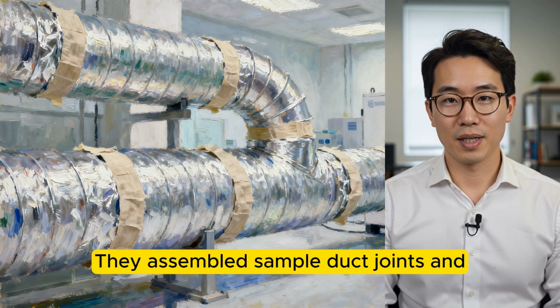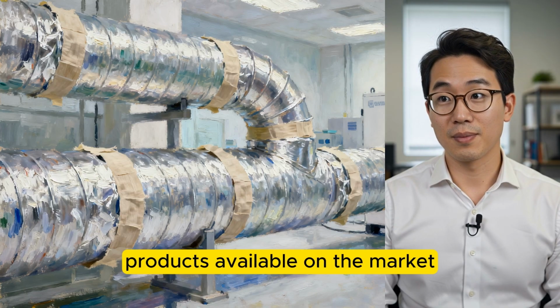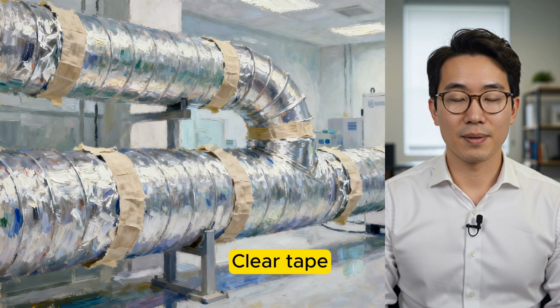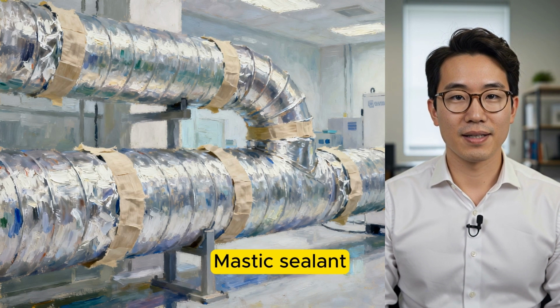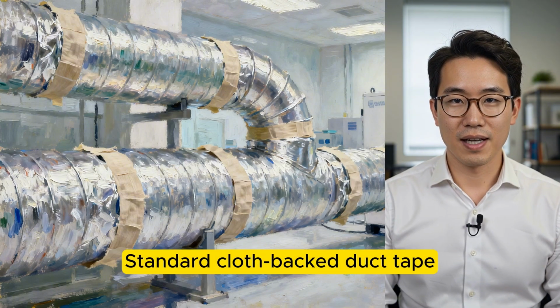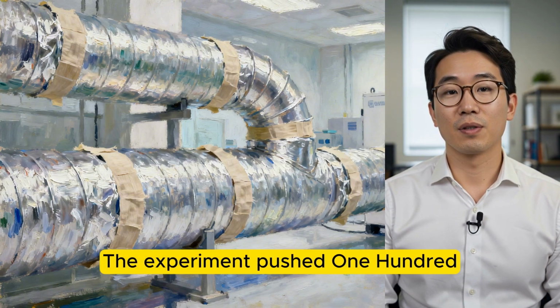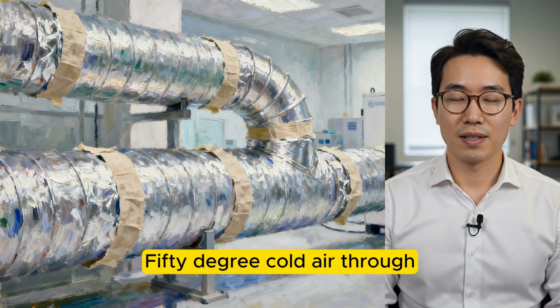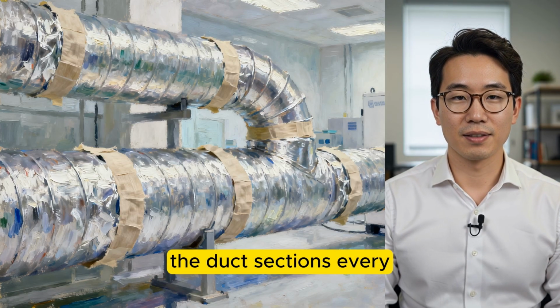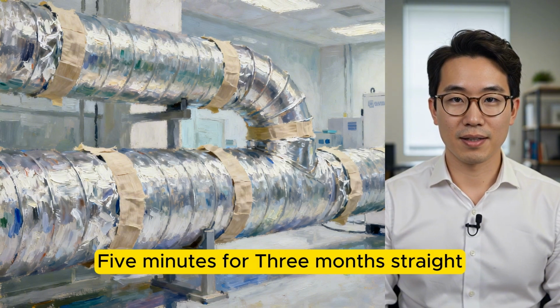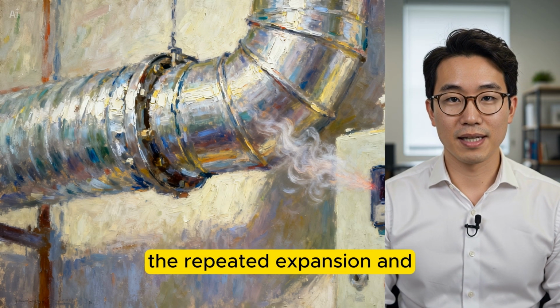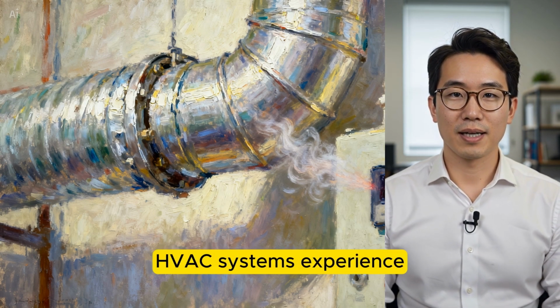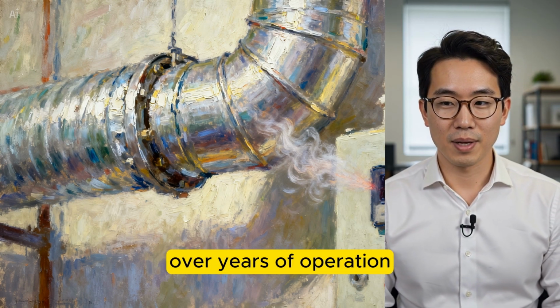They assembled sample duct joints and sealed each one using different products available on the market: clear tape, foil-backed tape, mastic sealant, aerosol compounds, standard cloth-backed duct tape. The experiment pushed 160-degree heated air and 50-degree cold air through the duct sections every 5 minutes for 3 months straight. The process recreated the repeated expansion and contraction real HVAC systems experience over years of operation.